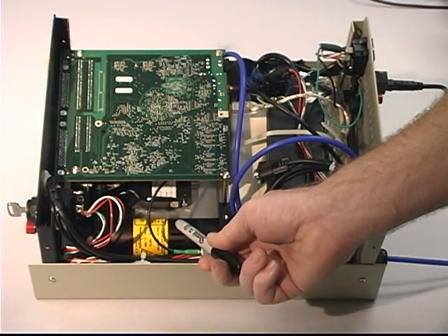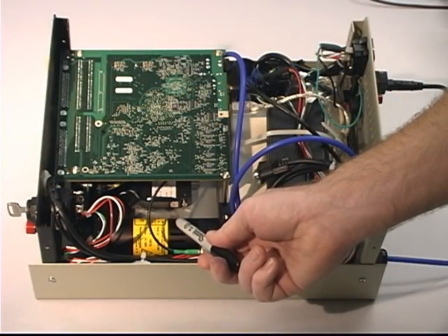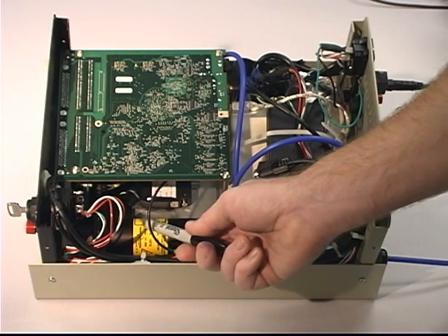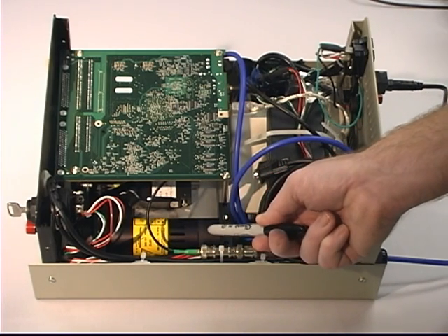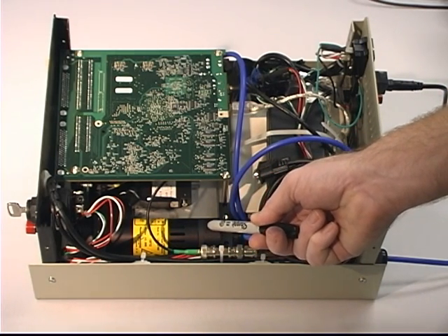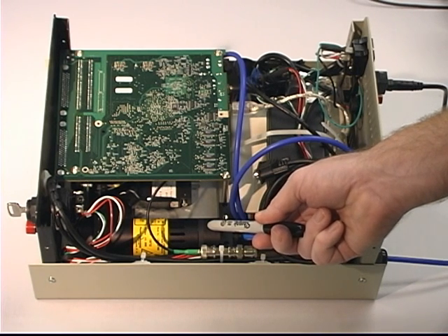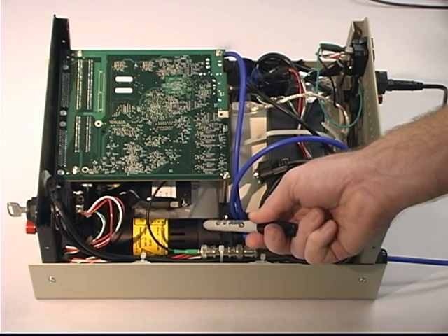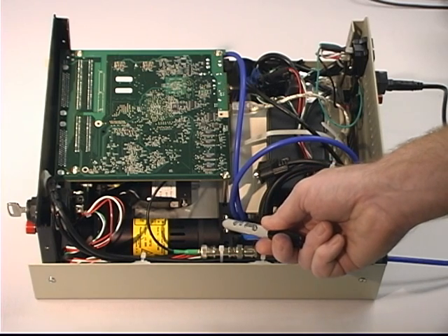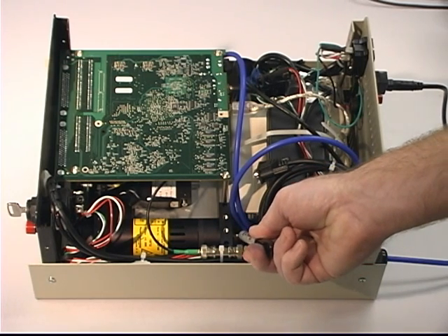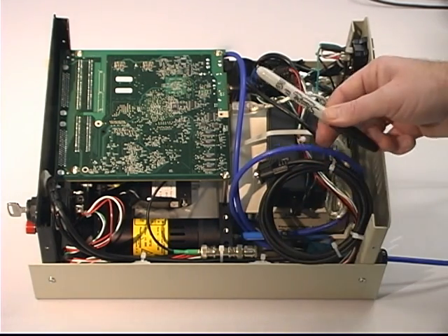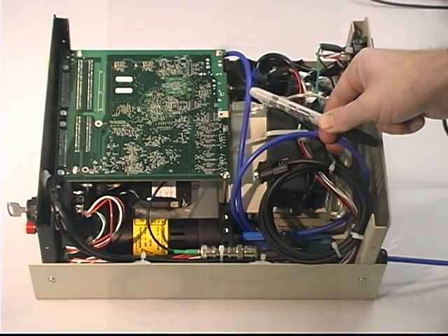While the diode laser is a Class 3B device and capable of emitting up to 50 milliwatts, the laser is operated such that light exiting the diode laser does not exceed 5 milliwatts. Additionally, the light exiting the F11 probe diverges rapidly. Any incidental light emitted from the probe or reflected off an aircraft surface is completely eye-safe.